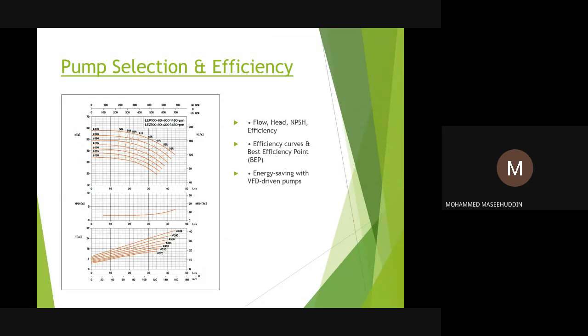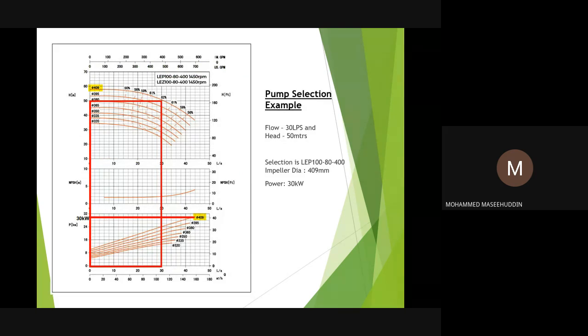Okay, so let's look at a typical pump selection. If you are looking at this performance curve, on the x-axis we have the flow rate, and on the y-axis we have the dynamic head indicated. And this is a typical example of one of the pumps with 1450 RPM, which runs on a 4-pole motor. I'll show you some selection which I have indicated here. Let us take one example of a flow rate of 30 liters per second and a dynamic head of 50 meters. Here the pump selected is model LEP100-80-400 with a 409 mm impeller diameter, and the power of the motor is 30 kilowatt.